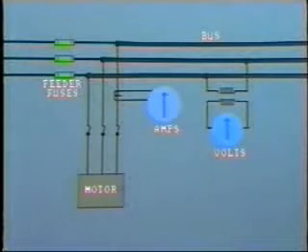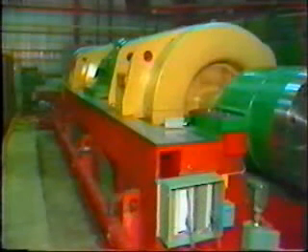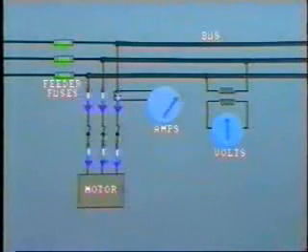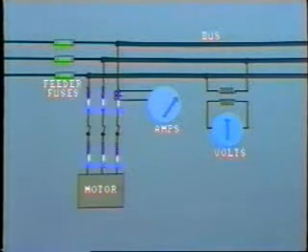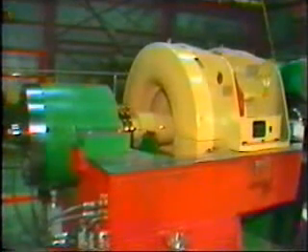We mentioned the problem of undervoltage. An even more hazardous condition can occur with complete loss of voltage, particularly on large, heavy machines. If the voltage is restored quickly while the machine is still running down in speed, an extremely large current will be drawn by the motor as it attempts to arrest the fall in speed and then accelerate the machine up to normal speed again. In some cases, this acceleration has even caused the drive shaft to break due to the inertia of the heavy machine.